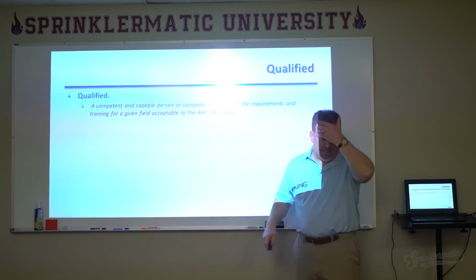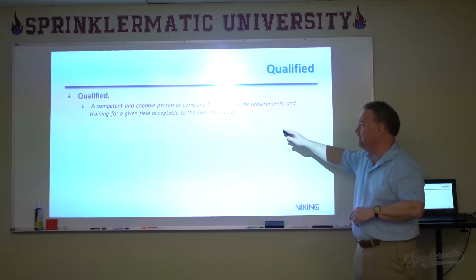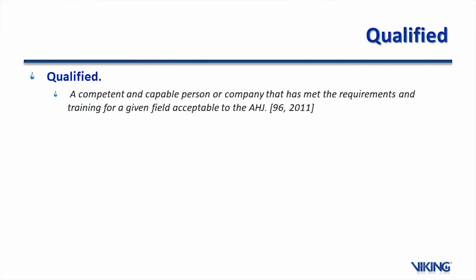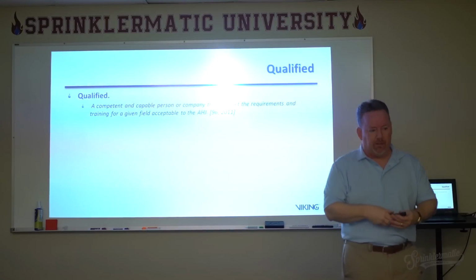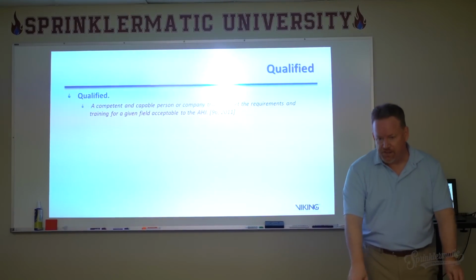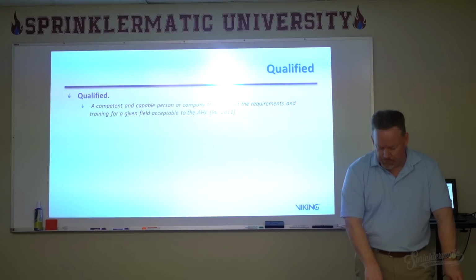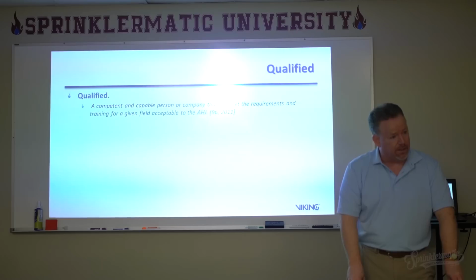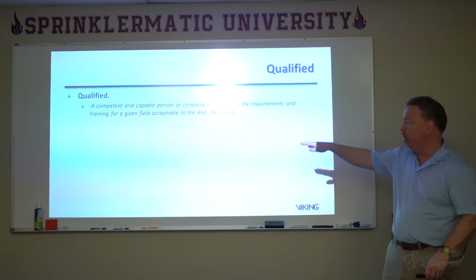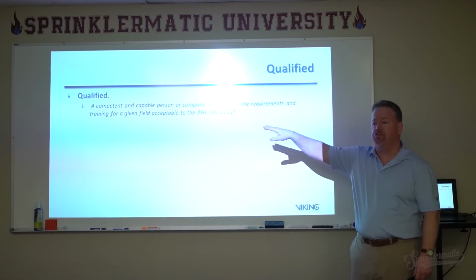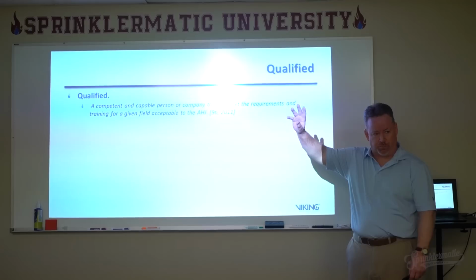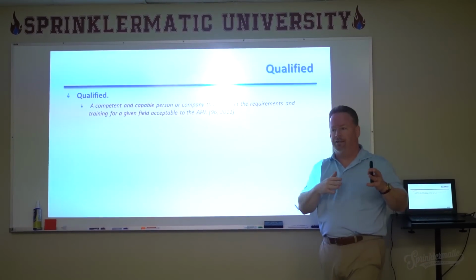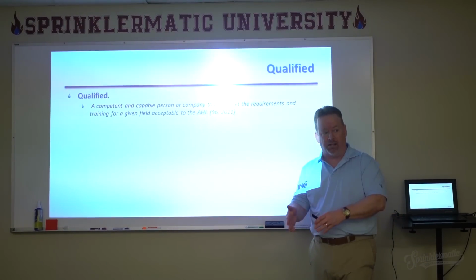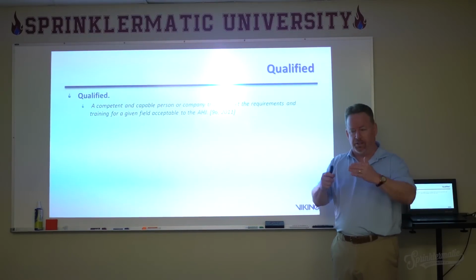The term qualified is defined in NFPA 25 as a competent, capable person or company that has met the requirements for training in a given field acceptable to the authority having jurisdiction. Be careful, because somewhere it says someone doing training, or someone doing inspection, probably needs to be trained, to be capable of doing that. That's far short of being qualified. Someone doing tests needs to be qualified, per the standard. So pay attention to where the standard uses terms like trained versus qualified, because qualified means something quite different. It's a higher standard.